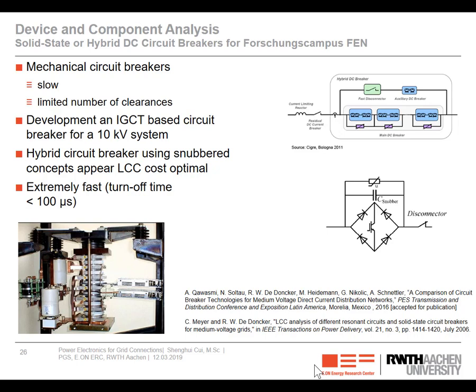And here this is the circuit breaker prototype constructed at our institute a long time ago, and in accordance with the test, it is possible to switch this fault current in a very, very fast speed, even lower than 100 microseconds. And of course, after the electronic switches are turned off, then we need to open the mechanical disconnectors. Then it takes a little bit longer time. I would say like several milliseconds.